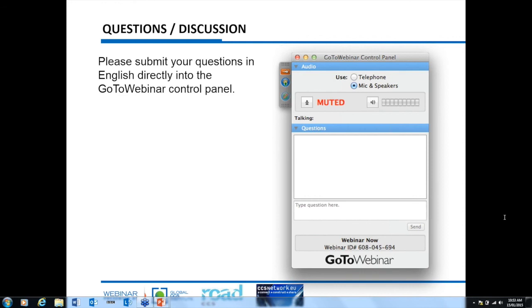That does actually give some extra mist formation. The mixed flue gas will be slightly oversaturated, and so we'll get slightly more condensation. So it'll be a slightly wetter stack than it was before. But it'll be slightly less buoyant because it's cooler. But that has all been modelled and permitted.